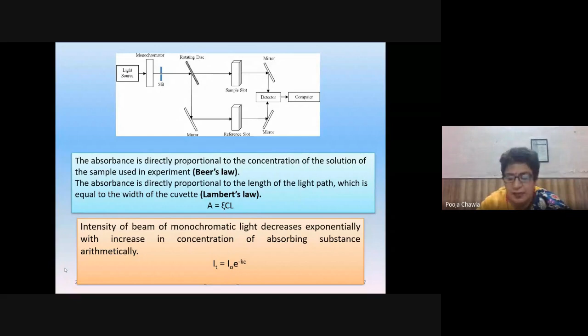Here you can see in the upper part, the monochromator chops the light from polychromatic to monochromatic. After that, with the help of the rotating disc, a part of the radiation will pass through the sample and the other will pass to the reference, that is the standard. After passing via the mirrors, they will go to the detector, and we can take the readings. In this example, you can see the intensity of the beam of monochromatic light.